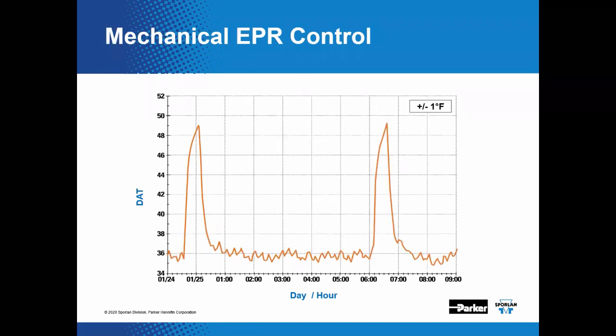Now here is the mechanical EPR. This is a log of data that was acquired on a system with this type of pressure regulator. Again, it was a medium temp system. We have discharge air temperature as time varies. The set point was around 36 degrees Fahrenheit. It varies about plus or minus 1 degree over time, which is not bad. It's just not as good as the other two methods. Correct.